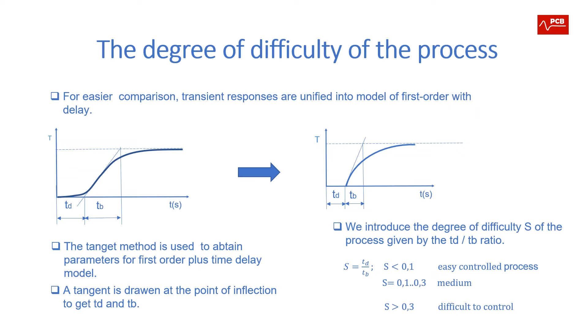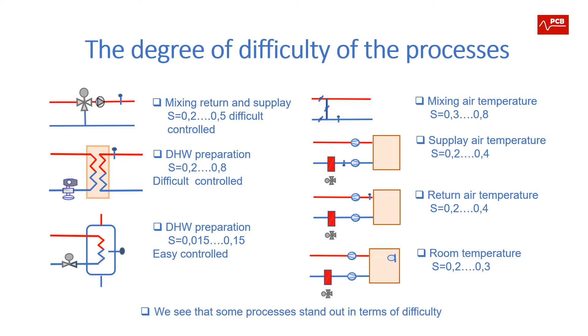Here we have a list of different kinds of processes, and we see that some processes stand out in terms of difficulty: the first one with the mixing valve where the sensor is far away from the valve, the process of domestic hot water preparation, and two processes in air conditioning—temperature control on the return channel and in the flow channel.